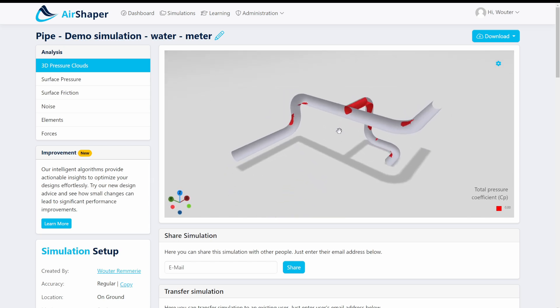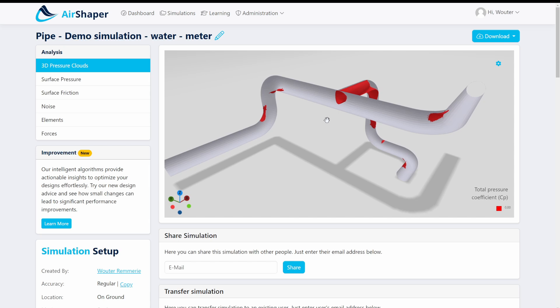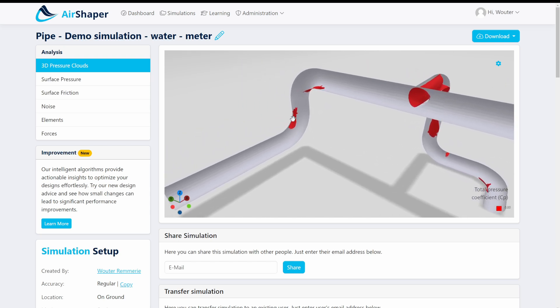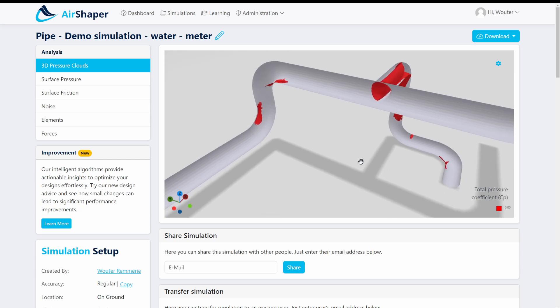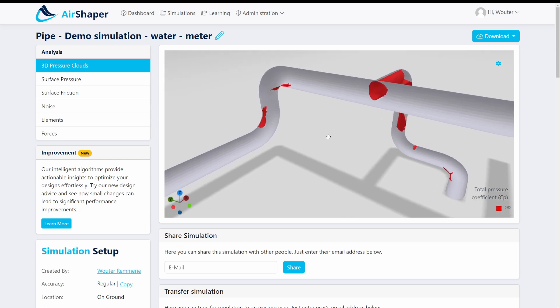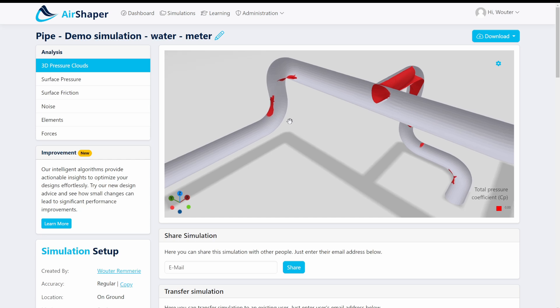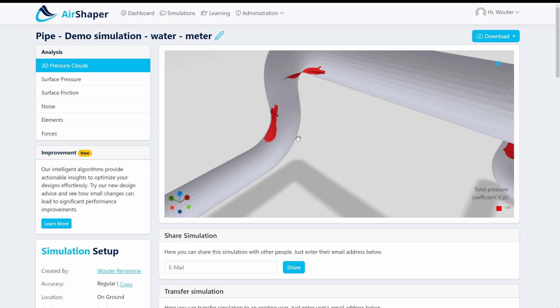So the first thing you want to analyze with this setup is where are we losing energy? Where are we generating a pressure drop? So if you look at this system these red clouds, it's an arbitrary threshold but this is a threshold for an isosurface for the total pressure coefficient of zero. So in normal terms what does this mean? This indicates in 3D where you are losing energy.